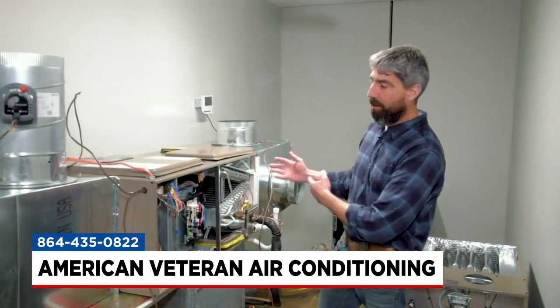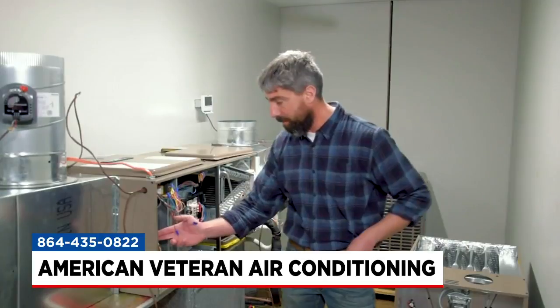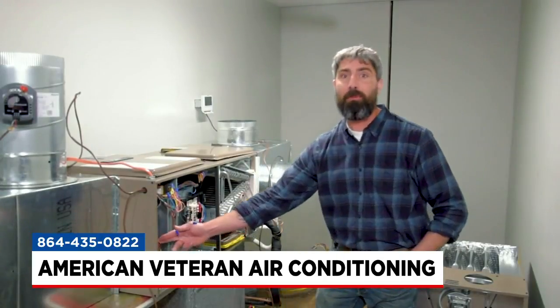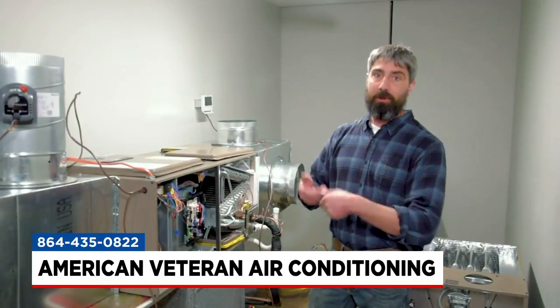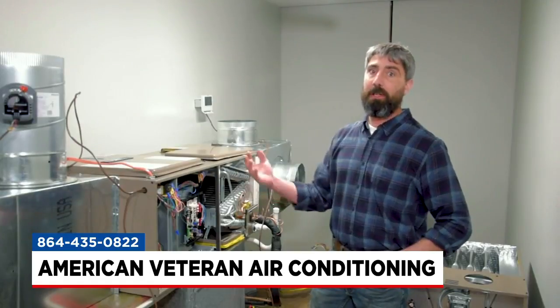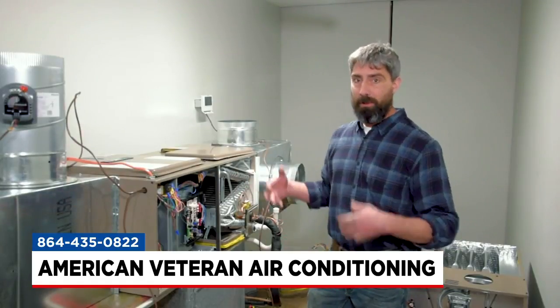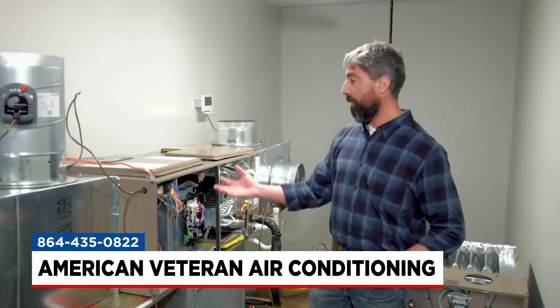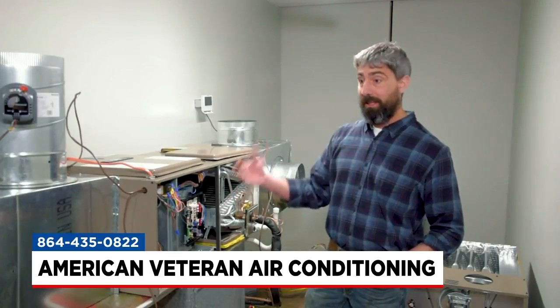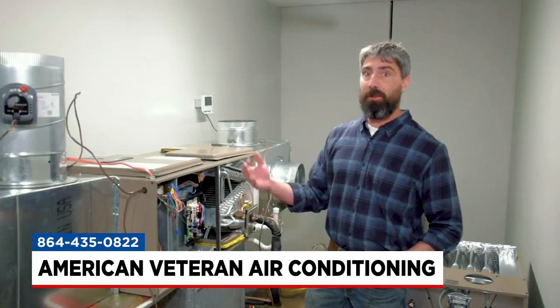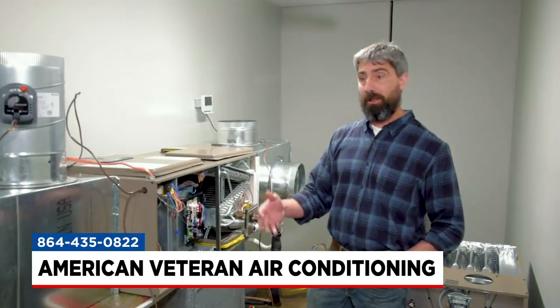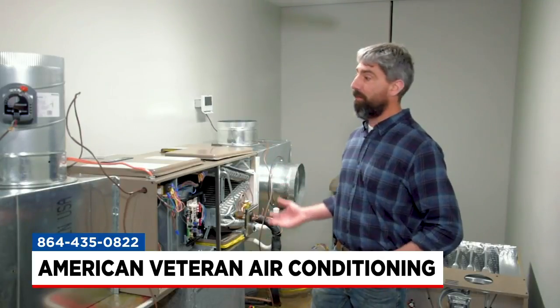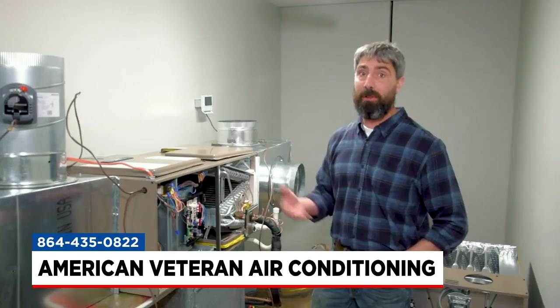The other big thing on a heat pump as well is making sure that your electric heat is operating properly, with all stages kicking in, the defrost cycle rolling the way it's supposed to, everything coming in together. One of the big problems we see a lot of times in the heating season is a unit being overcharged in the summer, and then it goes to the heating season and pressures just raise up like crazy. So that's a big deal.